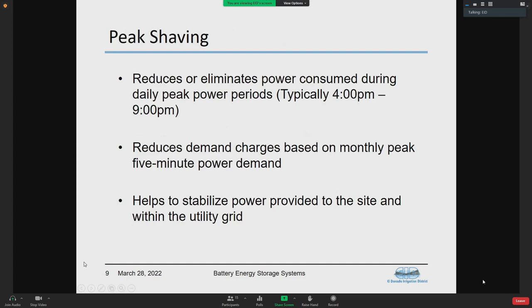In addition, the batteries normalize the energy coming into the site. Many of our sites have large pumps, and when those pumps fire on, it creates a huge spike in energy demand. The largest such spike each month results in a demand charge based on that peak usage. The batteries help normalize those spikes and reduce those charges on our monthly bill.